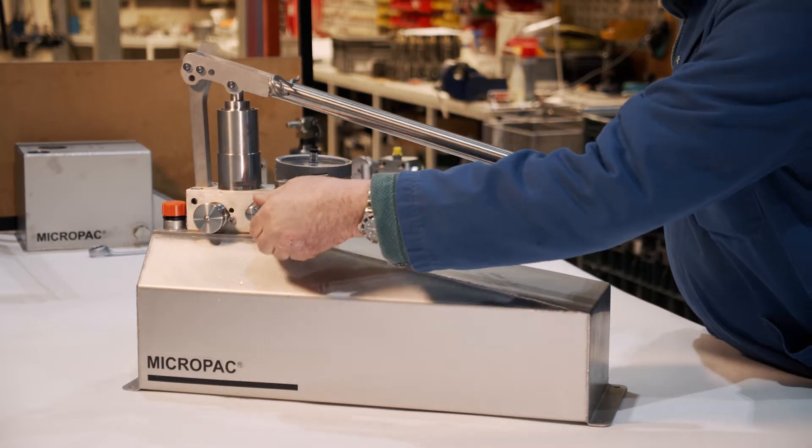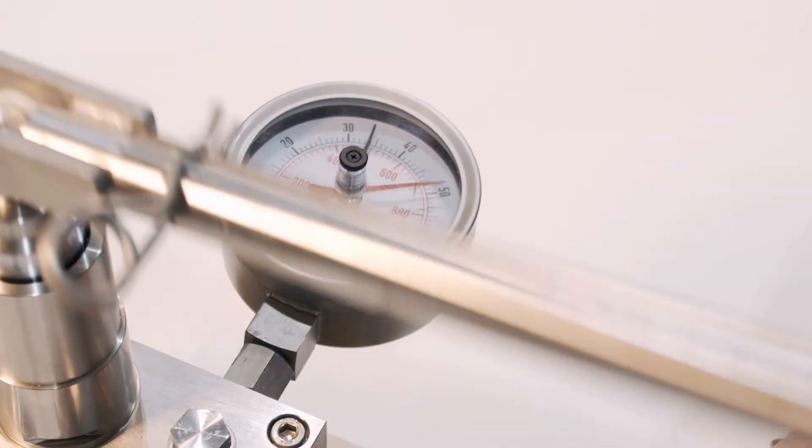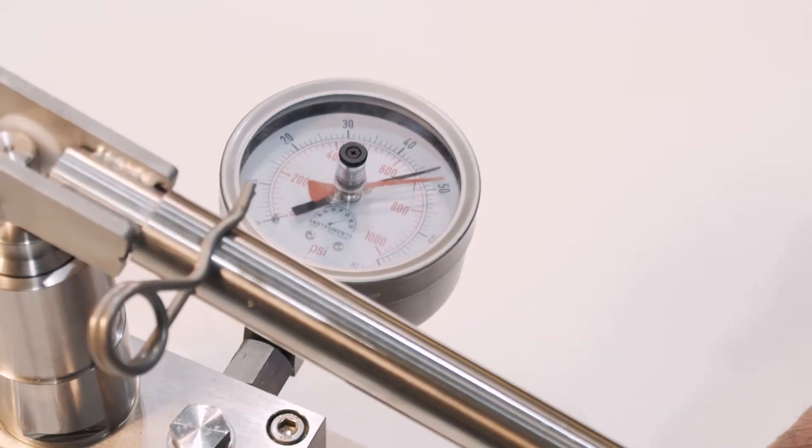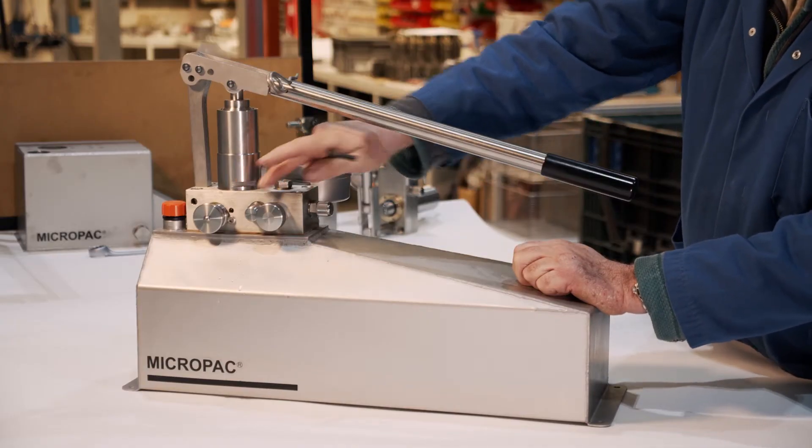Make sure the cap is on. Let's pump it up again. And there we are. 50 bar on our pressure gauge. That's how easy it is to set a Micropac relief valve.